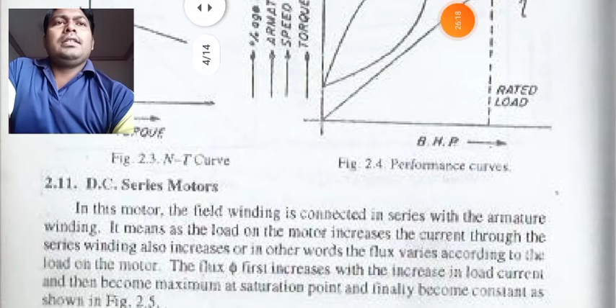Now, the DC series motor. Now we will discuss your DC series motor. In this motor, the field winding is connected in series with the armature winding, as we have already discussed in your machine subject, Energy Conversion 1. In this DC series motor, the field coil winding is in series with the armature. It means as the load of the motor increases, the current through the series field winding also increases.